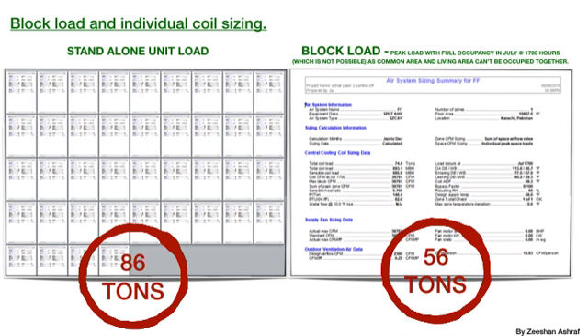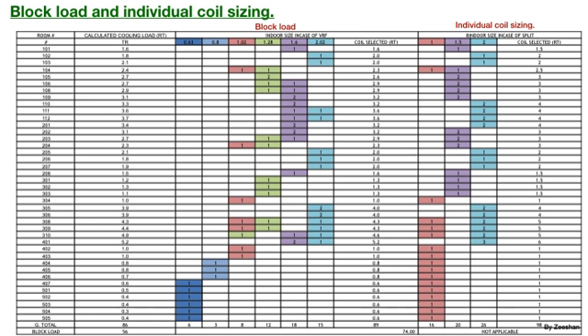We have performed load calculation. The output at left is according to standalone single split units, and the other output is according to the block load, that is, central plant AC VRF. The sum of all peak loads was 86 tons, however the block load is 56 tons. We selected the split units based on the nearest capacity model of split AC. The sum of selection becomes 98 RT. Then we selected indoor units for the VRF system. The sum of indoor capacity becomes 89 RT with total compressor size 56 RT.